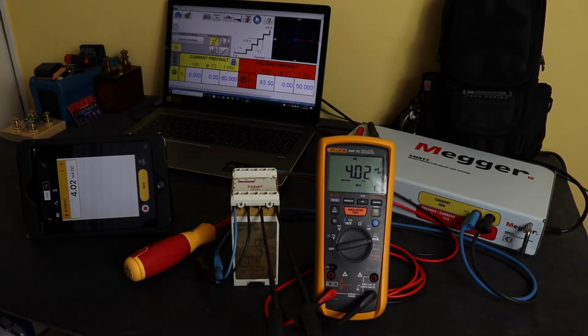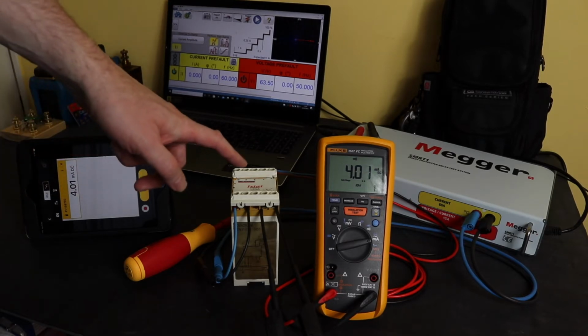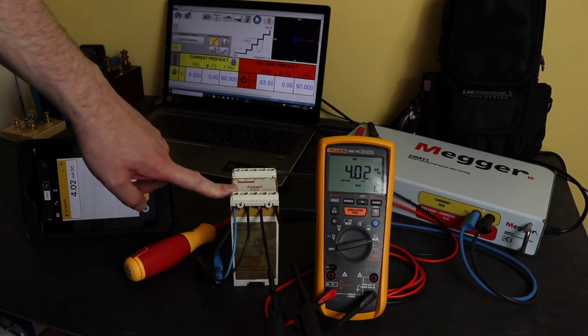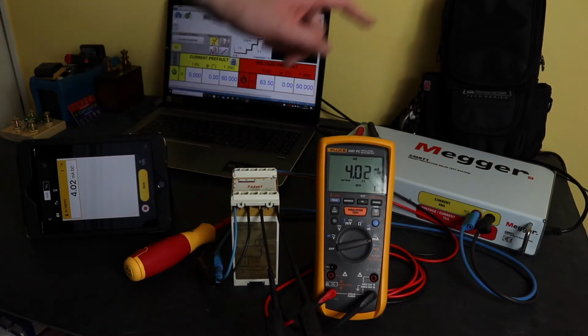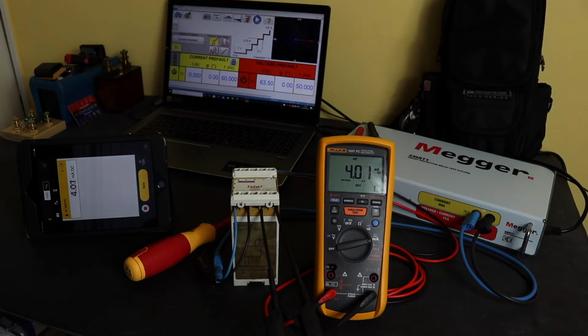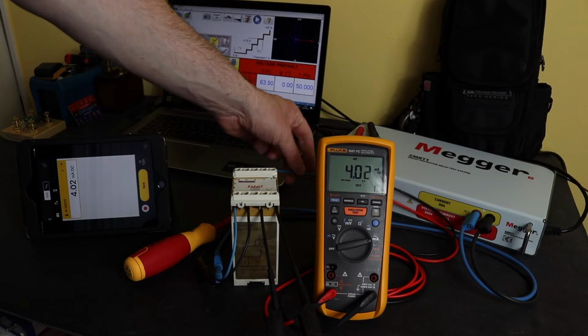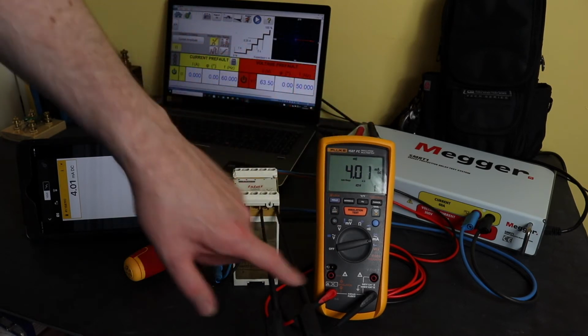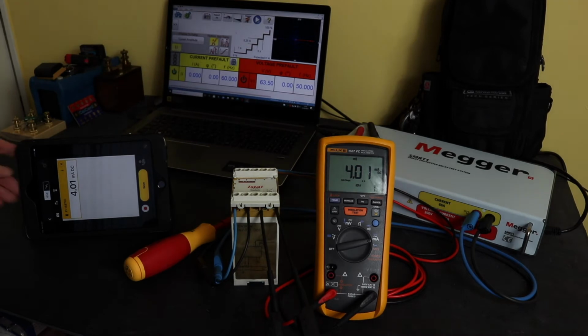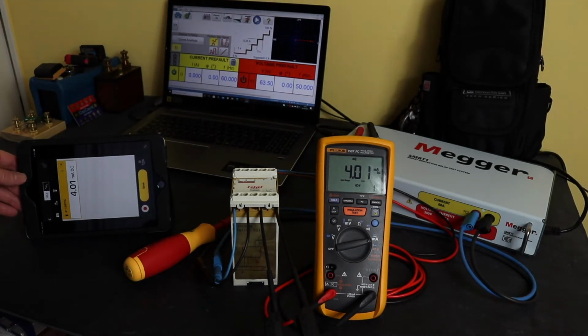This is an extension of the video I did fitting the Fluke 1587 FC into the Veto MB2 at the back there. So I was going to use this as my transducer test setup, and this is the test setup that I end up with in front of you here. The Fluke instrument is sitting there at the front alongside the current transducer. This one is 0 to 1 amp input, which is coming from the Megger SMRT1 over there at the back, and the output is wired here at the back into the Fluke set up on current measurement, and is actually transmitting to the iPad here.